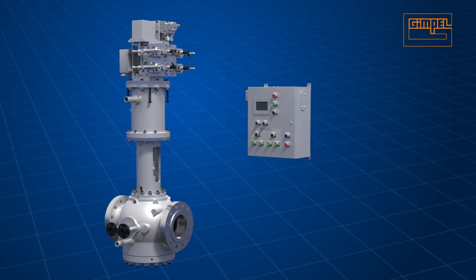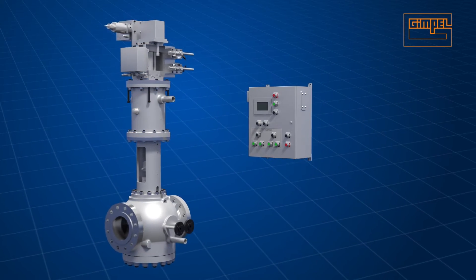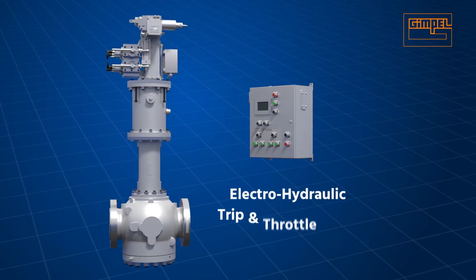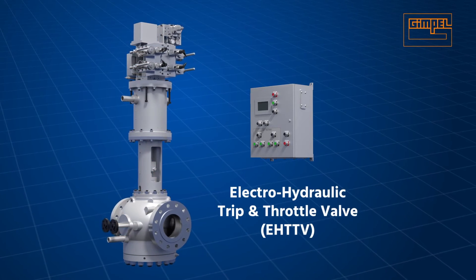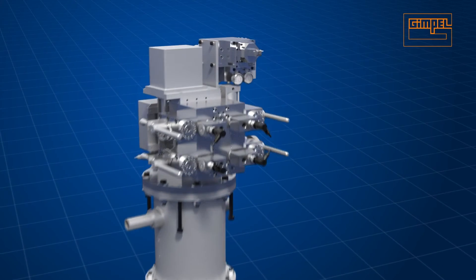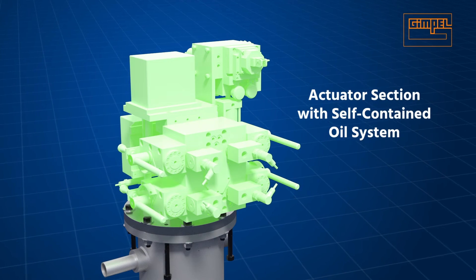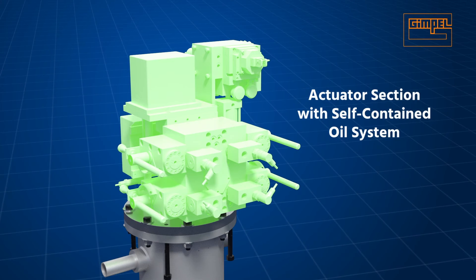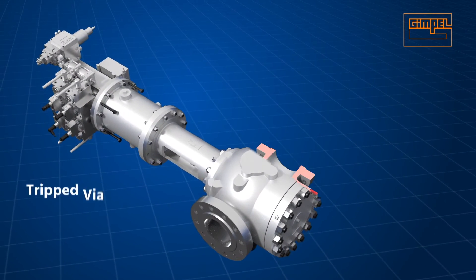Only one TTV currently on the market can address both the risk factors of existing types and the new regulatory requirements. That valve is the Gimpel electro-hydraulic trip and throttle valve, or EH TTV. The self-contained oil system isolates the EH TTV from potentially dirty and unreliable external oil supply.